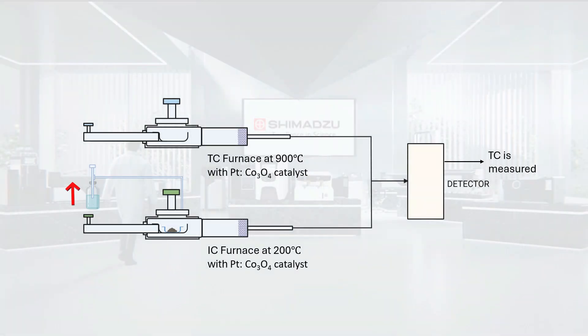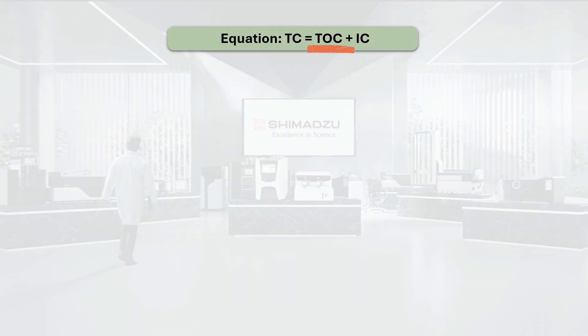When the acid is dispensed, it is directed into the sample boat, where it reacts with the sample. At this moment, the sample boat is pushed into the furnace compartment immediately. The reaction produces carbon dioxide and water. The carbon dioxide is sent to the detector for measurement, and finally the IC content of the solid sample can be obtained.